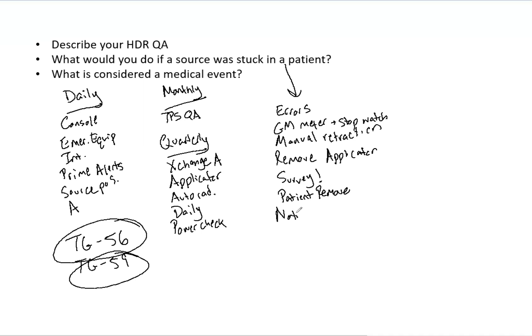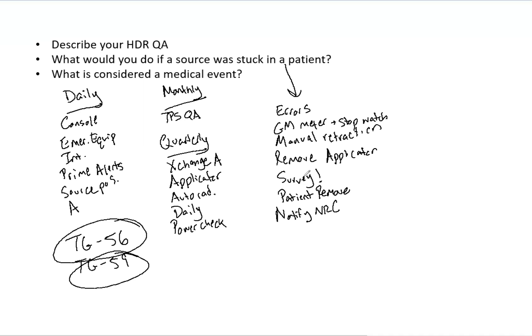Now you also, you need to notify the NRC verbally no later than the next day. And you also need to call the manufacturer of the afterloader. And then with the NRC, there's going to be some paperwork and documentation of what happened, what were the estimated exposure levels, things of that nature. You also need to notify the patient, the physician, and all staff as well, of course.